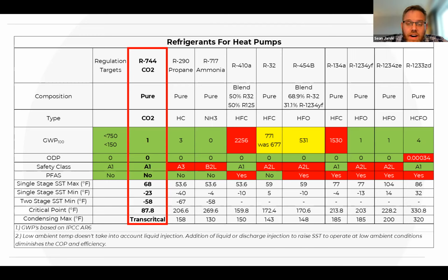So there are other options. 410A and 134A are great, safe refrigerants. But now you start looking at other natural refrigerants, such as propane and ammonia, going across the right, R290 and R717. Propane is explosive, meaning it will combust and explode. Ammonia is both mildly flammable and highly toxic. So there are challenges with both of those.